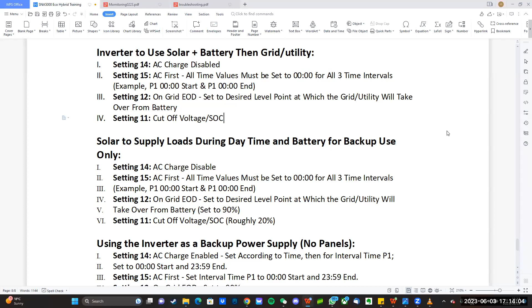For setting 14, AC charge must be disabled. Setting 15, your AC first tab, all values must be programmed as default, which is 0,0,0,0, for all three time intervals. For setting 12, your on-grid EOD, or on-grid end of discharge, set that to the desired level point at which the grid or utility will take over from the battery. For setting 11, program your cutoff voltage or SOC.